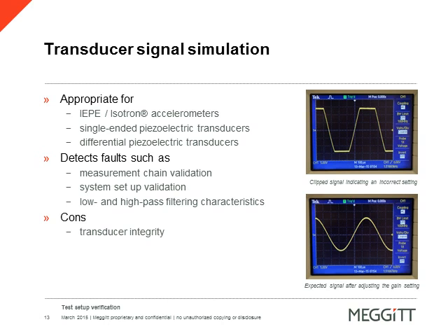Certainly, Ray. We can perform a similar test method for charge simulation and insert in place of the piezoelectric accelerometers. Meggitt incorporates the functionality as well in the 4830B for both single-ended and differential piezoelectric accelerometers. The handheld unit simulates the output in charge mode accelerometer in picocoulombs for complete channel setup. The signal is adjustable in frequency and in amplitude, making it a very dynamic test that can identify channel noise as well as verifying out-of-band frequencies to ensure appropriate filtering is enabled.